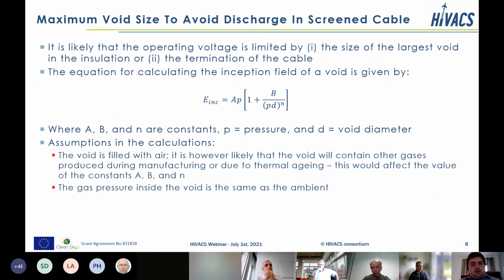So we then considered that the operating voltage might be limited by something else, and something else in this case could either be a void within the insulation, or indeed it could be the termination of the cable and the issues that we've already discussed around the screen cut. So there's an equation that gives the inception fields for a gas-filled void, and in this equation A, B and N are constants, and these depend on the gas and the void diameter, and then we've also got pressure and void diameter in the equation as well.